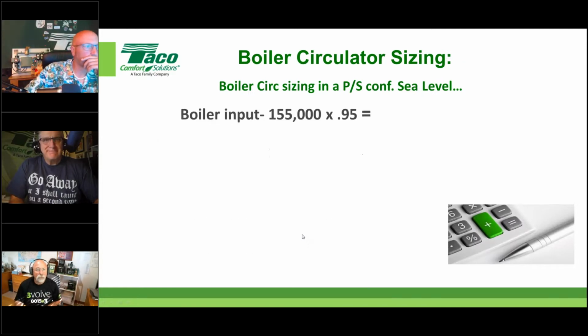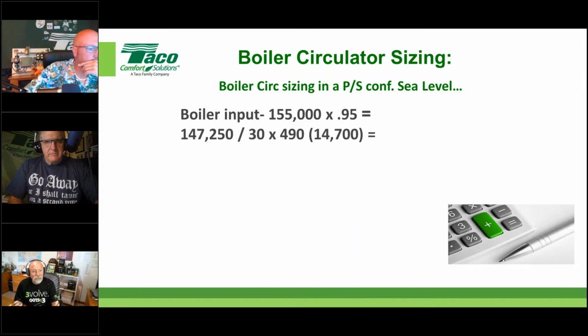So anyway, boiler circulator sizing at sea level. We're not going to show you the high altitude stuff. We're just going to jump right in. Same boiler, 155. Let's say it's at an AFUE listed 95% efficiency. We take that 147,250, which is nothing more than this times this, right? And we divide it by a delta T of 30 degrees. I'm just saying that's probably a good starting point as long as the manufacturer lets you, and widen it if you can, okay? 490, just pretend it's 500 if you don't know what 490 is. All 490 is just 500 in a high temperature.